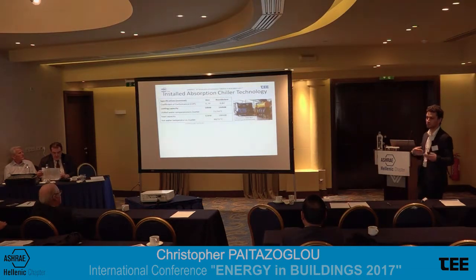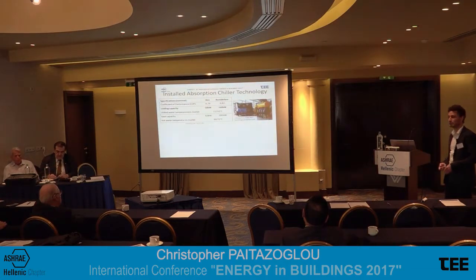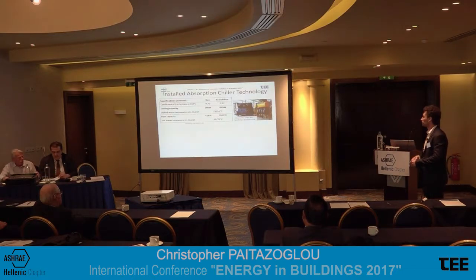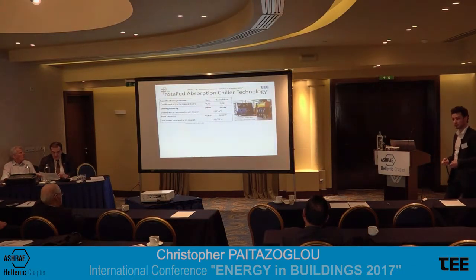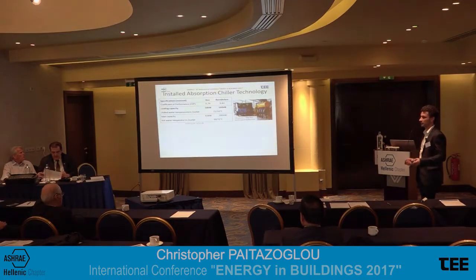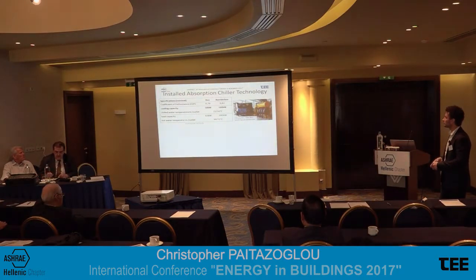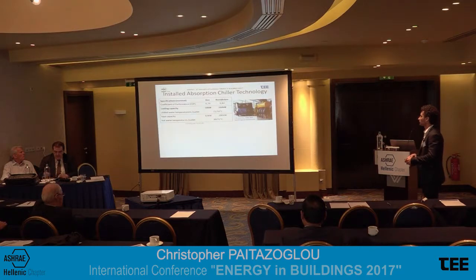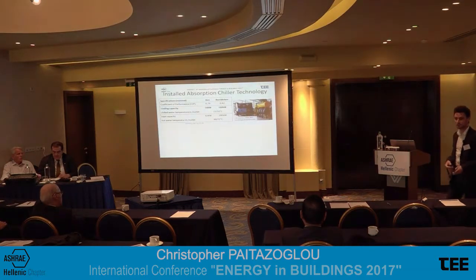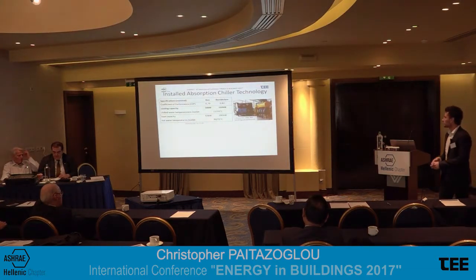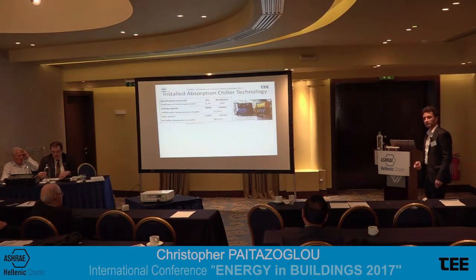When I talk about absorption chillers, there are 2 types of chillers that we have developed and brought into the market with a manufacturer. They are called Beak and Bumblebee, funny names, but it applies to their capacity. So the Beak can provide 50 kilowatts, the Bumblebee 160, at a rather good COP, not to say outstanding COP, but keep in mind that they are providing chilled water at a high temperature level, 21 to 16, and cooling down the hot water from 90 to 72.